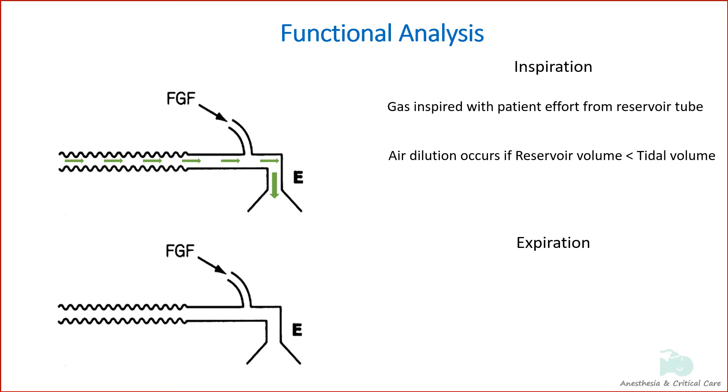In such case, the semi-closed system of Mapleson E becomes semi-open system. During expiration, both exhaled and fresh gas pass into the reservoir limb and then to the atmosphere.